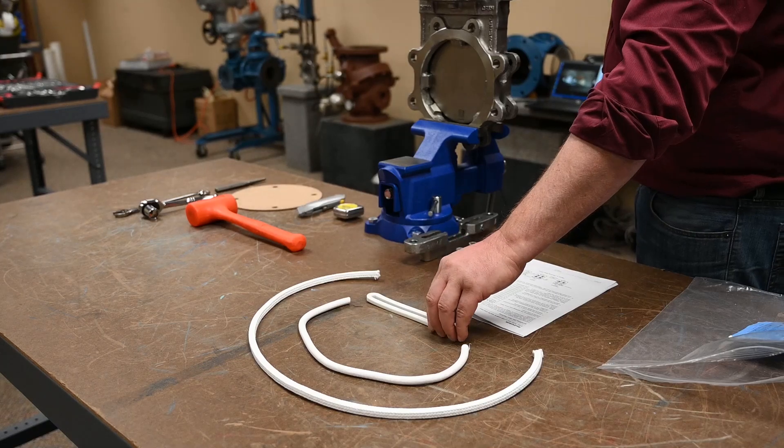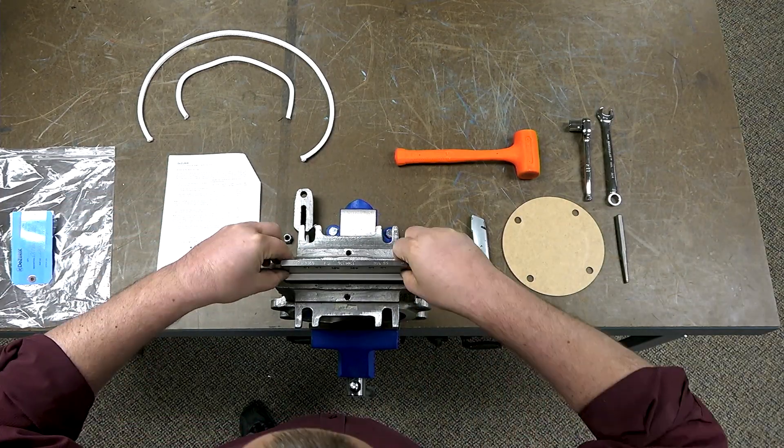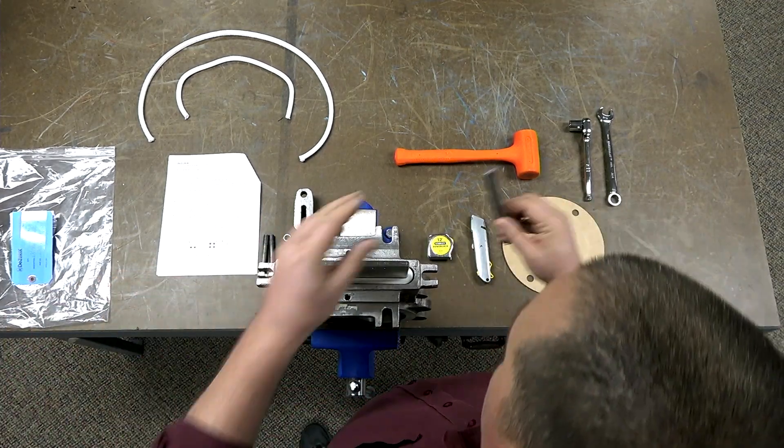Insert the anti-extrusion ring around the gate. Gently push the ring down into the packing chamber using a plastic or wood square end punch to avoid marking or damaging the gate.